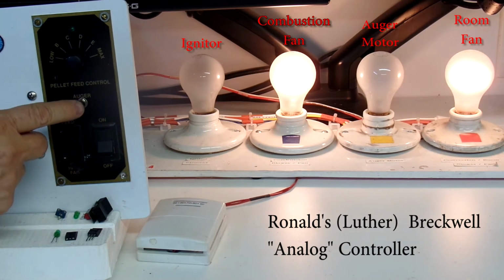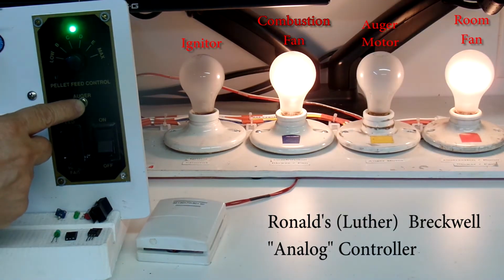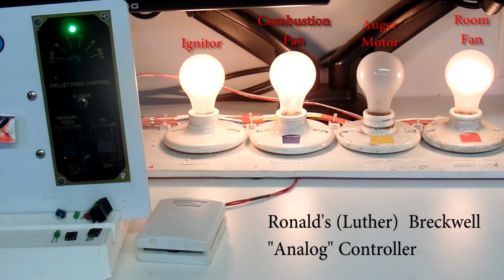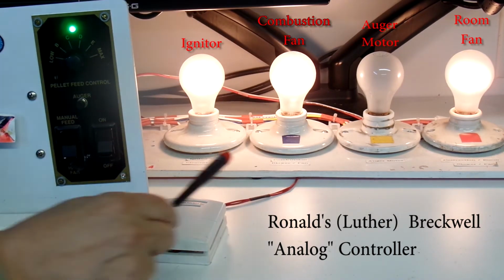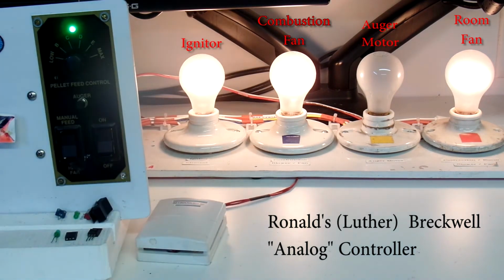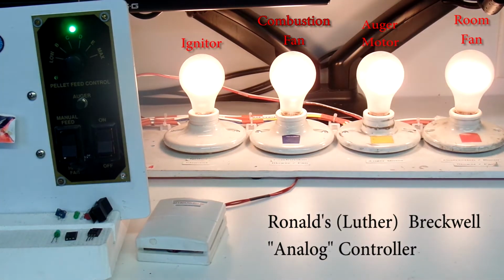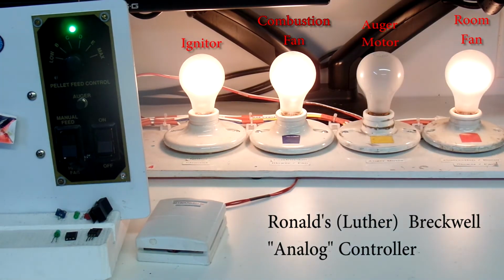So let me go ahead and start all this. As I press the button, we see the green light has come on. We had a quick spin of the auger and I'm going to release, and the timer has started to determine when the first cycle of the automatic auger drive will come on. Let's wait for that to happen. Since we're in low, it'll be a long time and the drive period will be quite short. Let's wait for that to happen. Very short drive period, notice that. We'll wait for one more cycle of that so you know how long it takes.